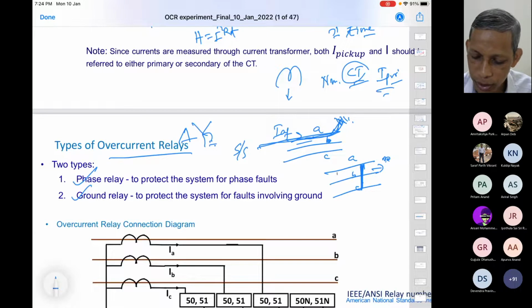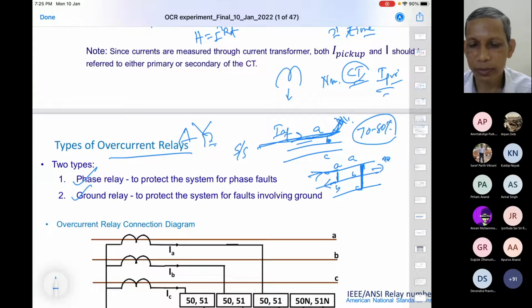Suppose two phases are involved, phase A to phase B. Currents from here to here, IA and IB, will both be of the same magnitude. The current will be high between these two. There is no ground current here. But ground faults are more common. 70-80% of faults involve ground. Agree? So we will see that.